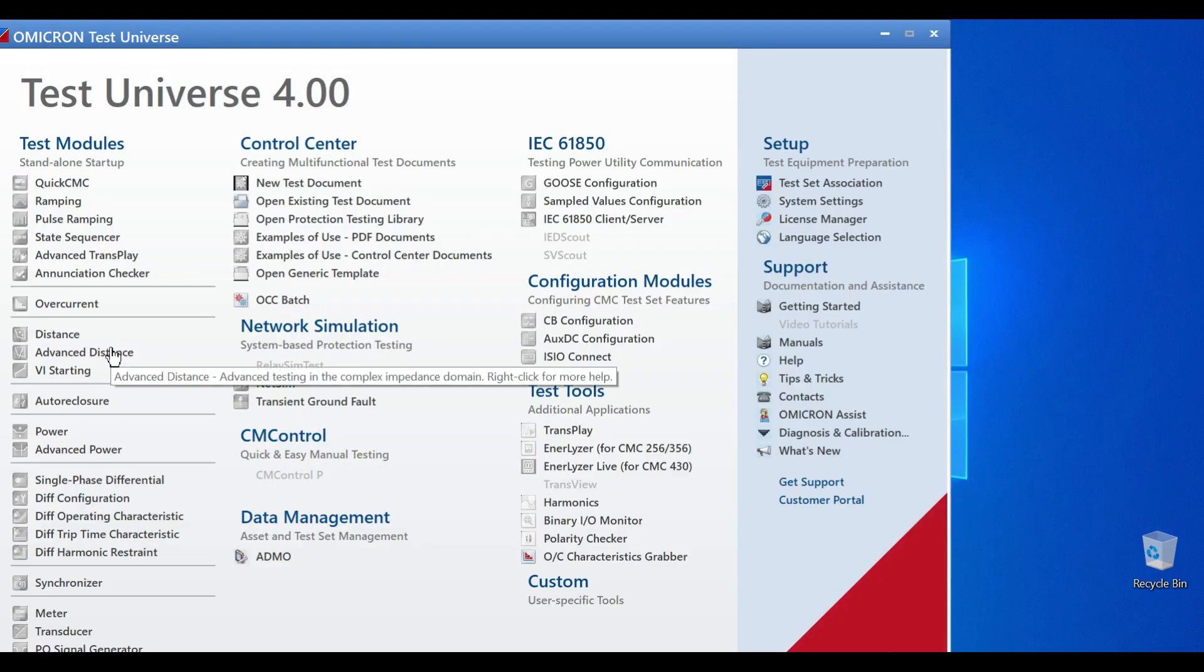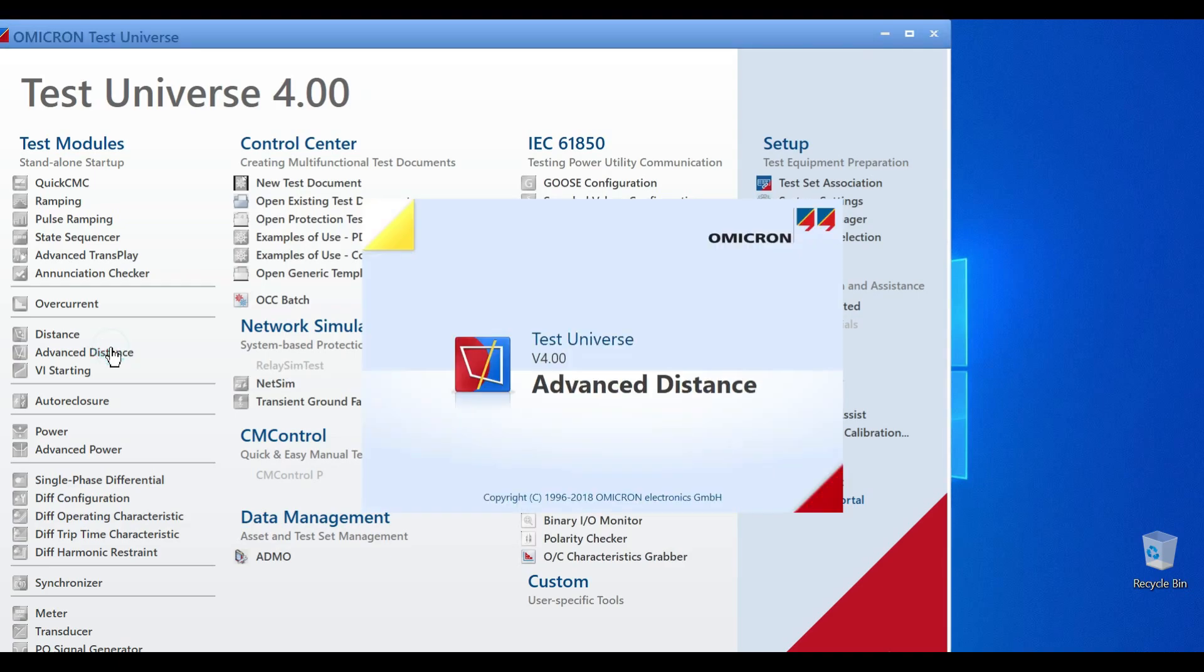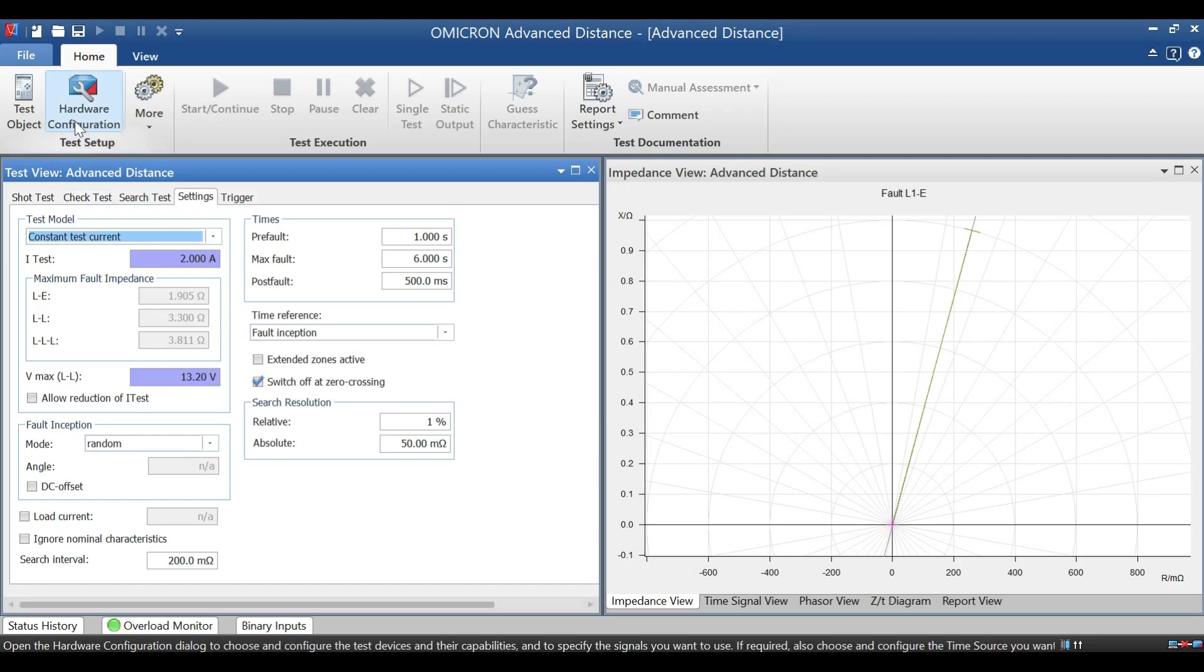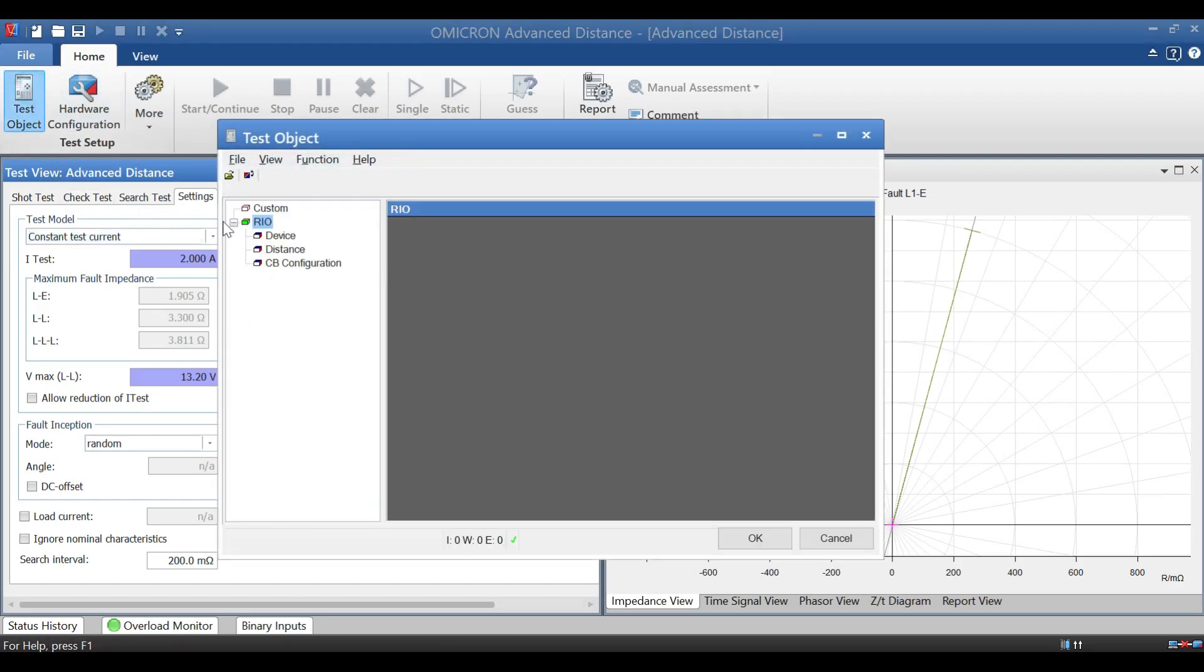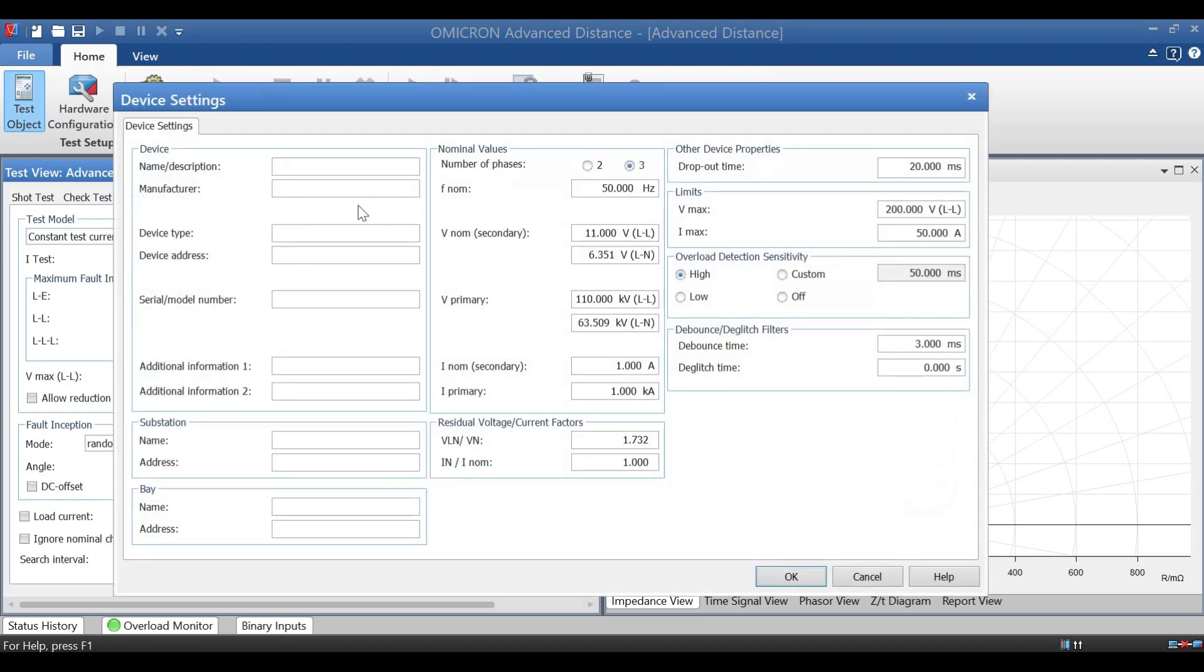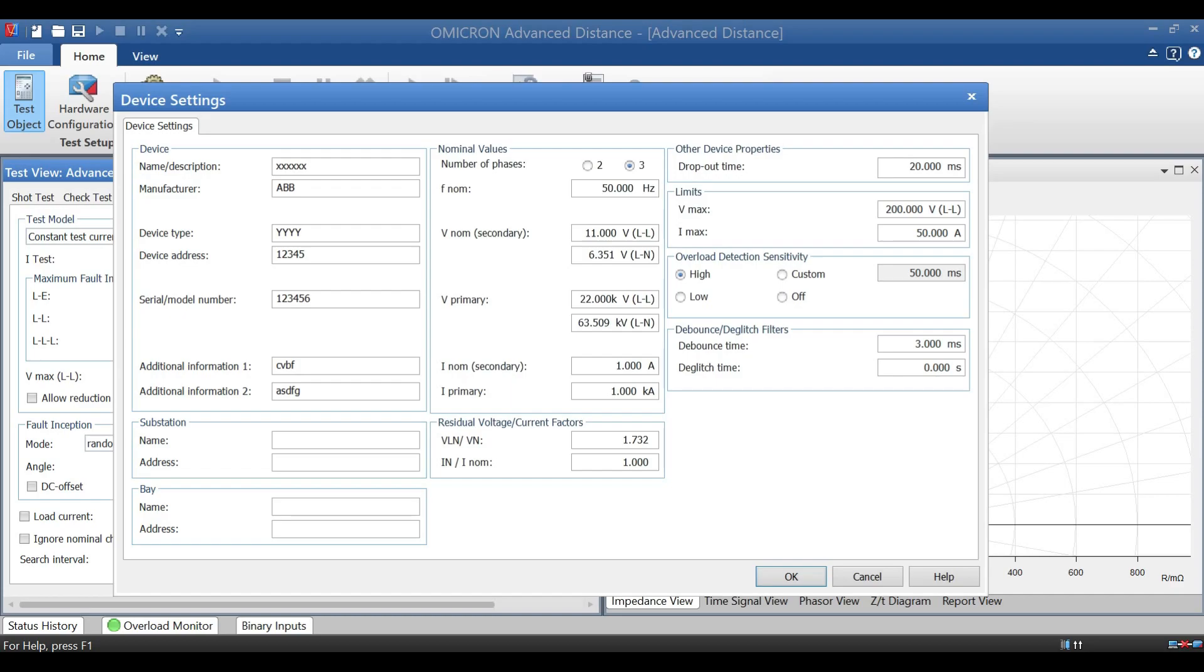Now we will see how to test the relay by using Omicron kit. First, double click the test universe, then go for advanced distance option. In advanced distance, we have to go for test object. In test object, first we have to fill the value for the device. So for that, just click edit and fill your power plant detail over there. Next, filling voltage and current value is very important. We have to fill according to our plant.